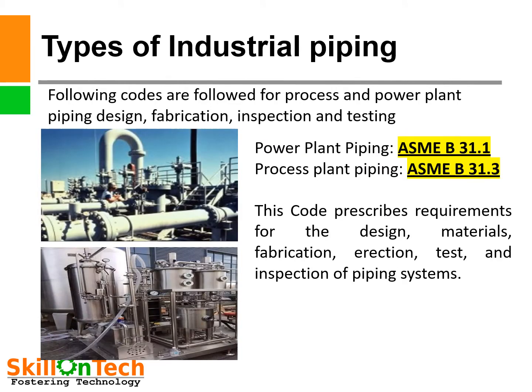Types of industrial piping. The following codes are followed for process and power plant piping — design, fabrication, inspection, and testing. A picture of power plant piping is shown at the top of the slide, where steam power lines and hot lines of condensate have been shown. Power plant piping is done as per ASME B31.1. Process plant piping is done as per ASME B31.3. This code prescribes requirements for the design, materials, fabrication, erection, test, and inspection of piping systems.